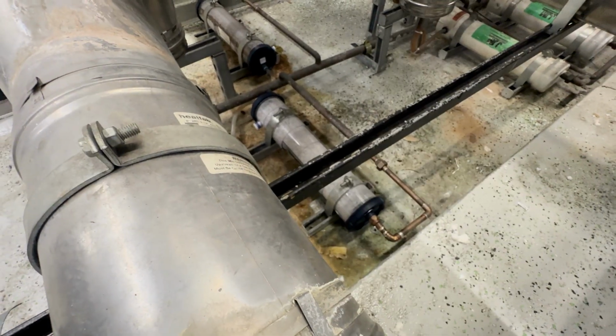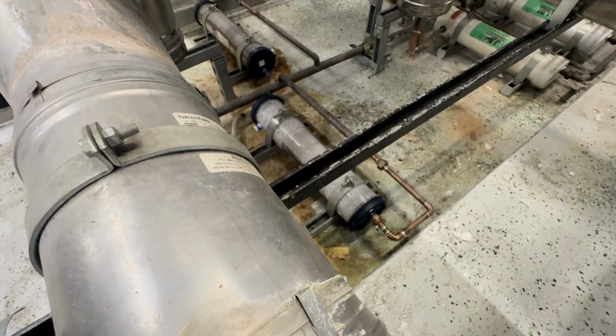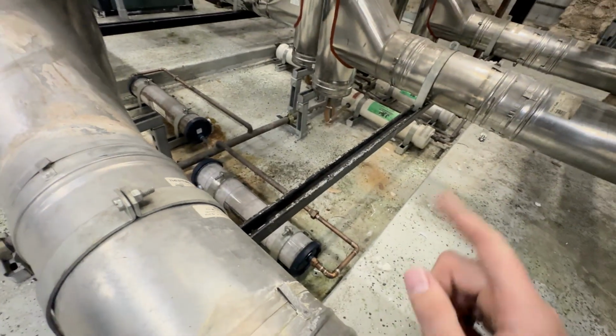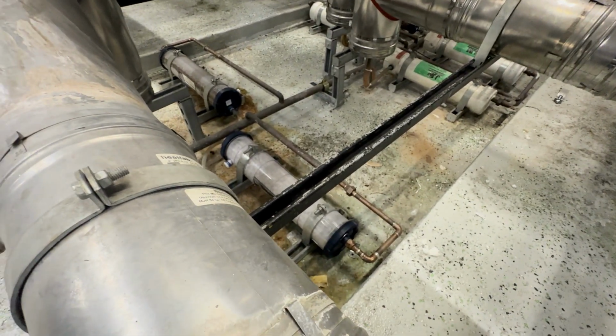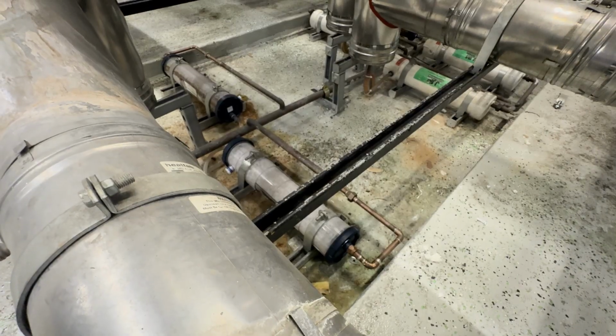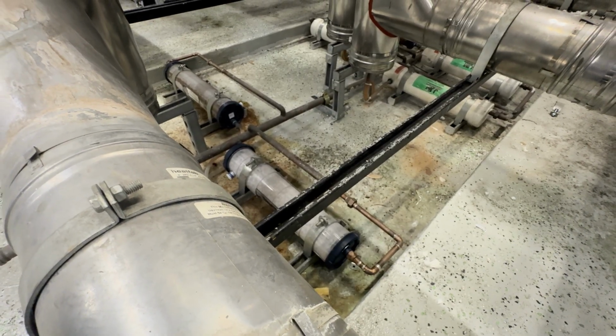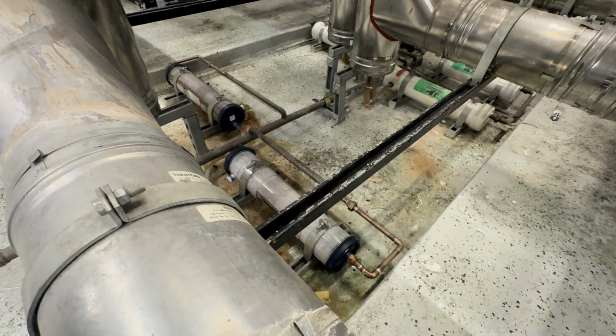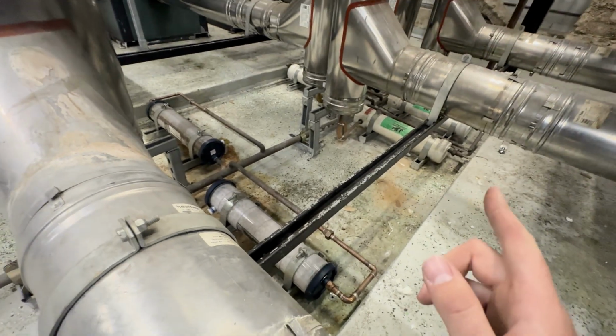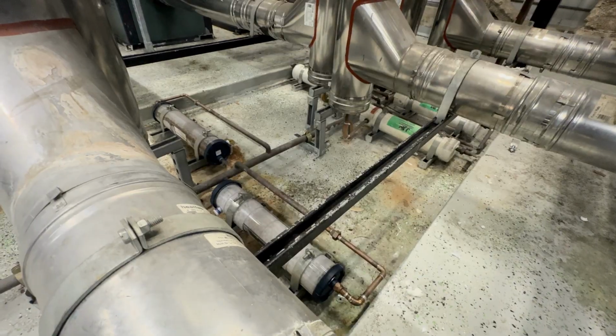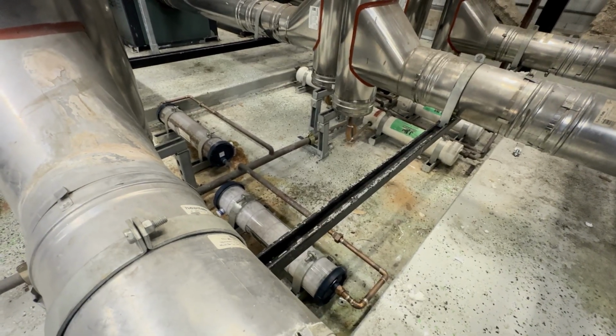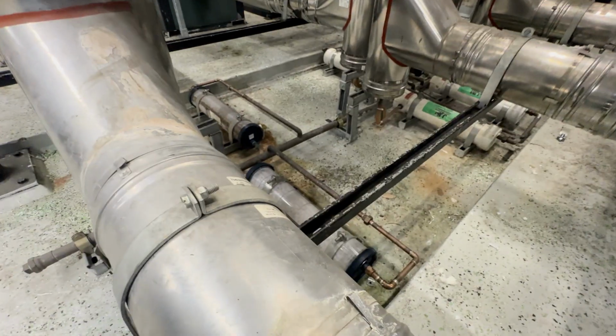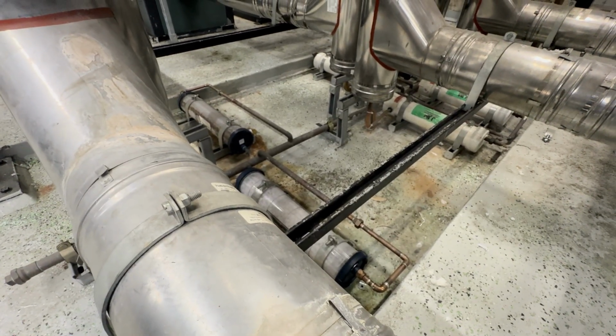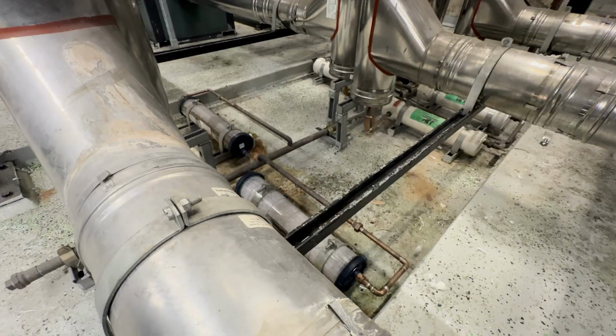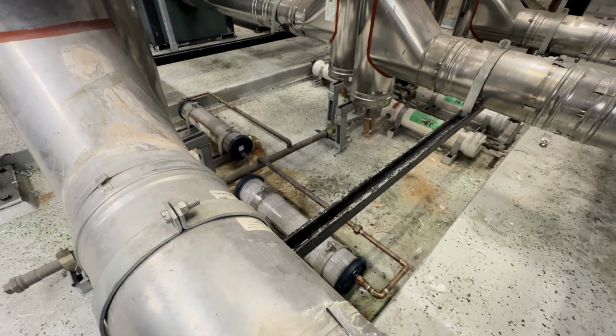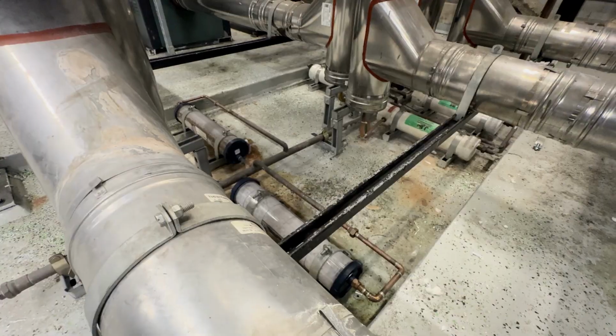This was newly installed not too long ago, so we know it's fine. For some of our older units like that one over there, you want to crack them open, inspect the rocks on the inside, make sure they're not too degraded or not really dirty. Other than that, you can buy the rebuild kits for those. They're just bags of pebbles that you clean the old ones out, wash them out, and then put new ones in. For residential use, you should probably replace them like every 6 to 12 months, but for heavy commercial like this, we really replace them every 3 to 6 months, so quarterly to biannually.